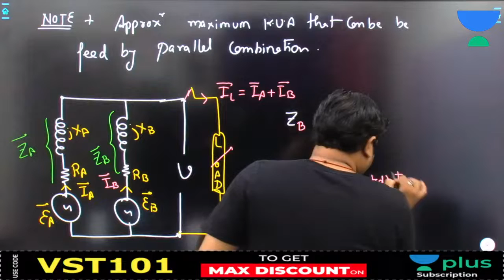Maximum load that this combination can feed is the rated KVA of the transformer which is going to be overloaded first. So what is rated? Voltage V into current delivered by transformer A is rated. However, voltage V into current delivered by transformer B is not rated, because the impedances are different. So definitely more current will flow through transformer A and it will get overloaded first.